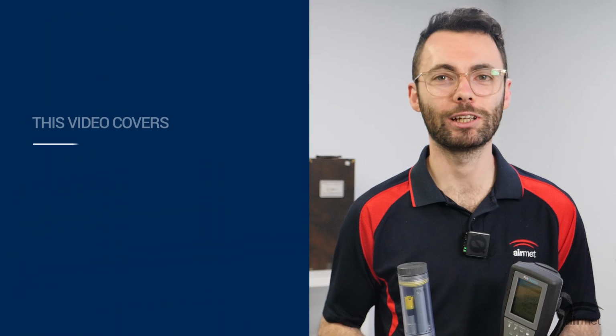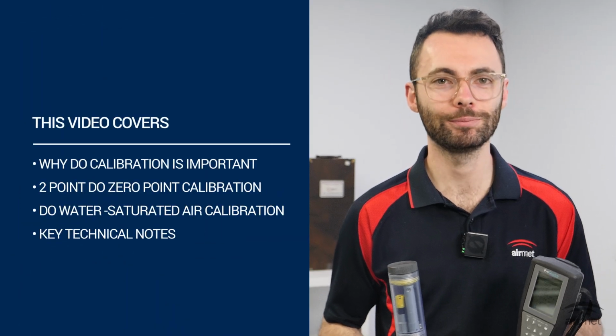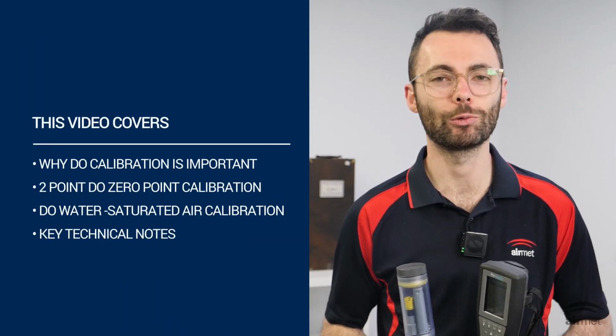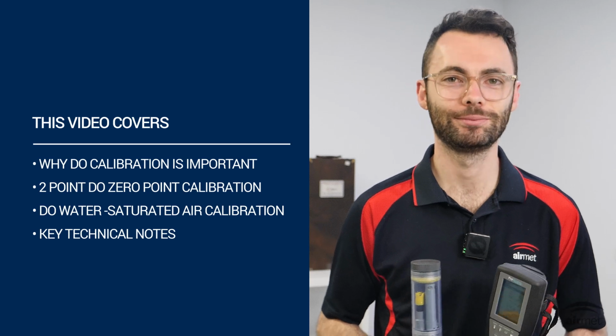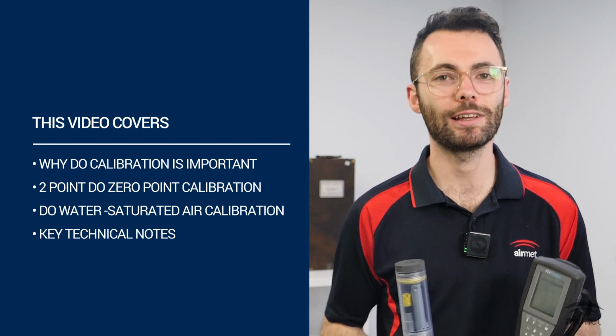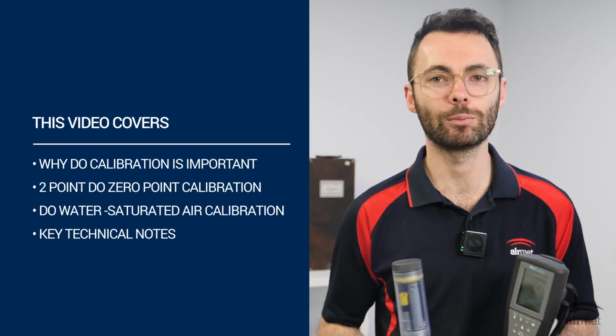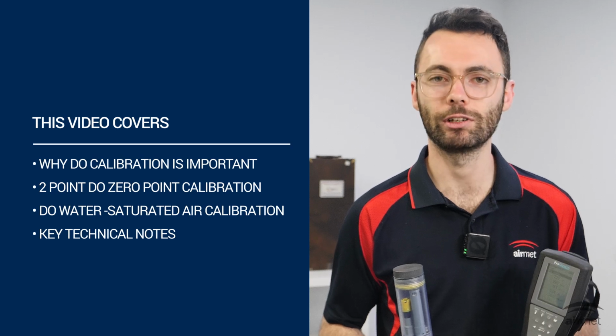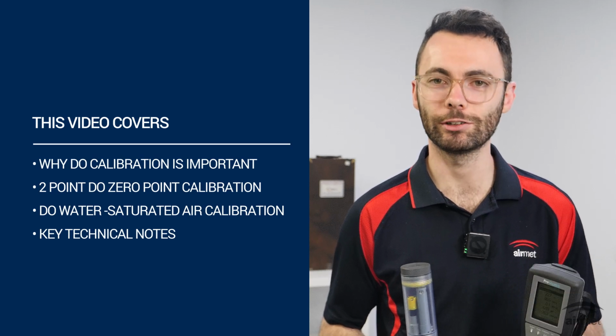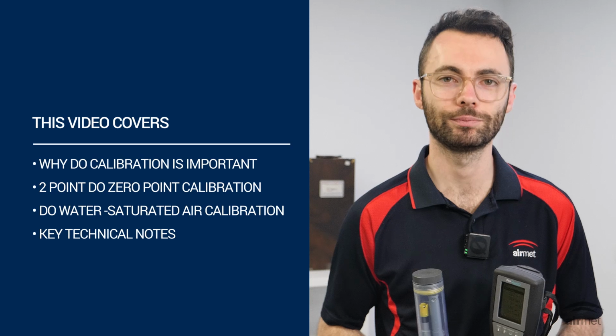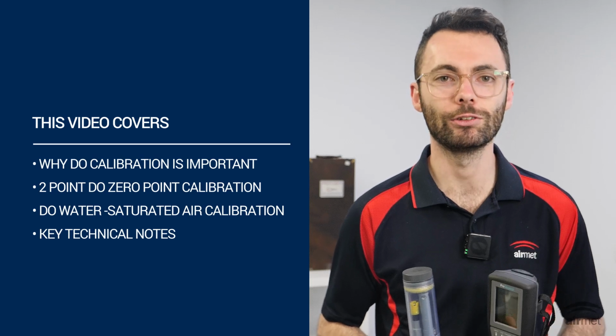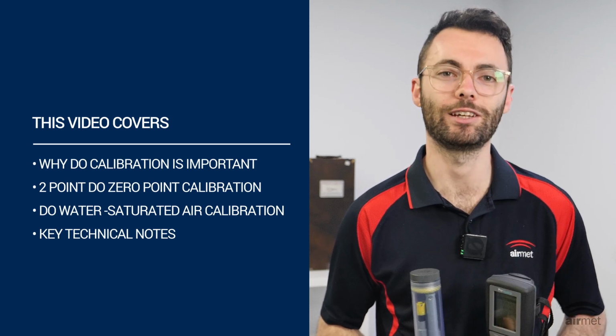In this video, we'll explain why DO calibration is so important, how the different calibration options work, and when to use them. We'll walk through how to set up a water-saturated air calibration, how to complete a milligrams per litre calibration using a known standard, and how to run a zero-point calibration when required. By the end, you'll know exactly what to do to keep your DO sensor performing at its best.